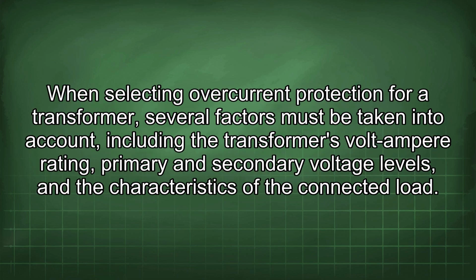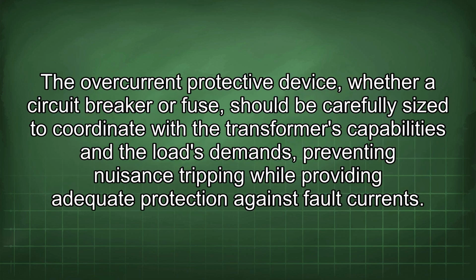When selecting overcurrent protection for a transformer, several factors must be taken into account, including the transformer's volt-ampere rating, primary and secondary voltage levels, and the characteristics of the connected load. The overcurrent protective device, whether a circuit breaker or fuse, should be carefully sized to coordinate with the transformer's capabilities and the load's demands, preventing nuisance tripping while providing adequate protection against fault currents.